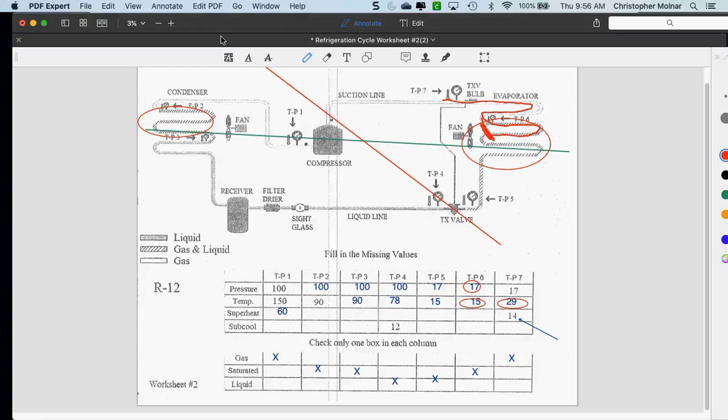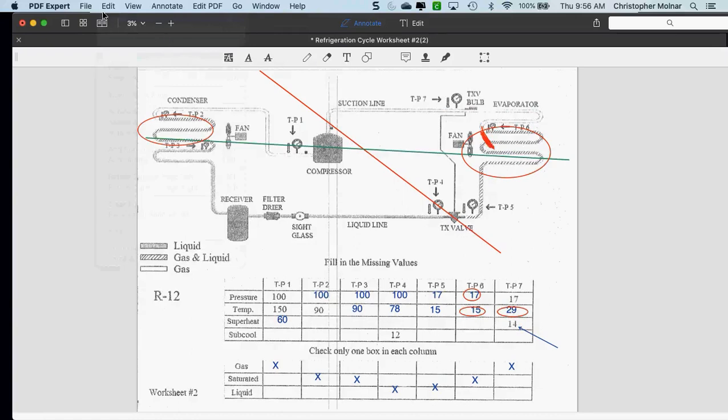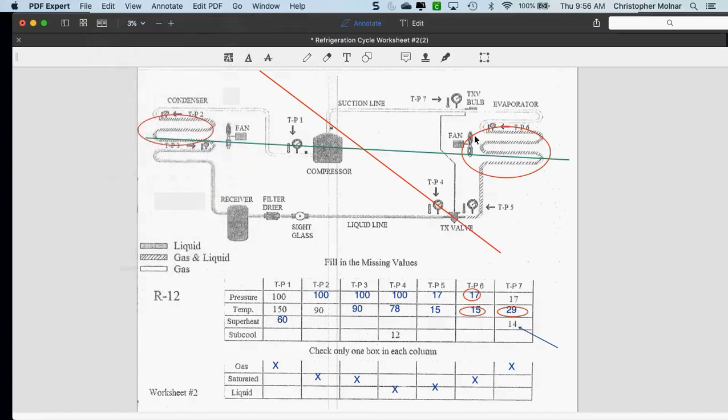So when we're talking about superheat, and adjusting superheat and controlling superheat, all we are doing is changing the amount of refrigerant that's in the evaporator. And again, tomorrow we'll talk more about evaporators and that whole thing. But I'm adjusting superheat. I'm changing the amount of refrigerant that's flowing into the evaporator.